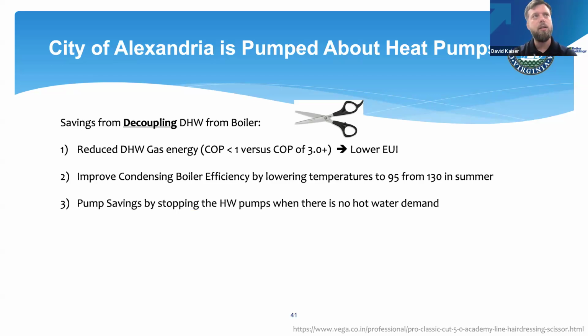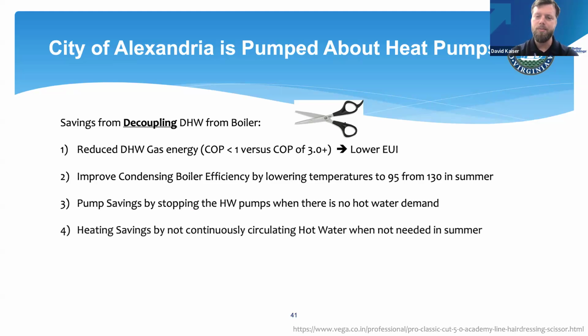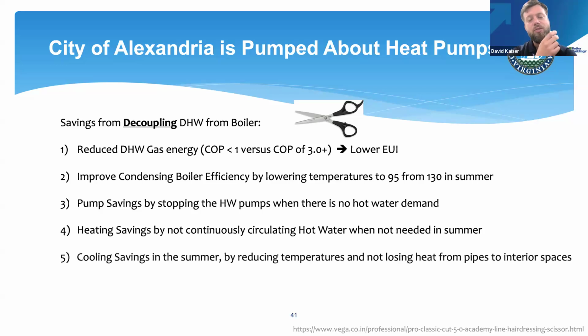So now we don't have to run the hot water pumps throughout the entire building when there's no hot water demand. So again, that's probably the biggest savings of this entire project, not the heat pumps themselves, but the pump for the entire building that we can now turn off because we don't need those pumps running anymore if there's no demand. Next, we've got heating savings by not continuously circulating the hot water. We've got heat loss through all those pipes going through the building by having that pump on all the time.